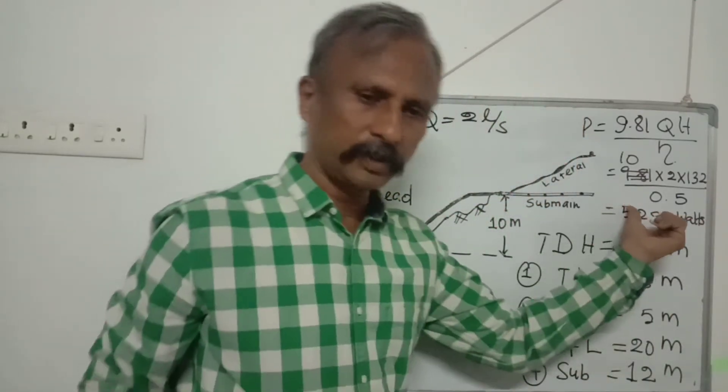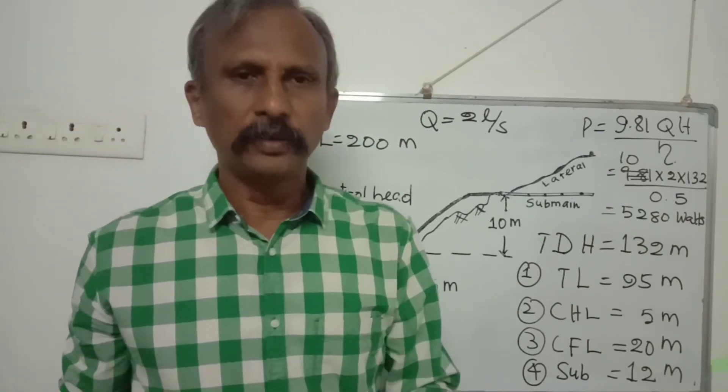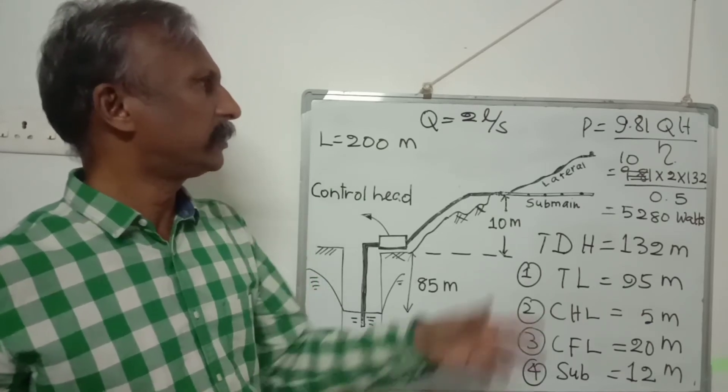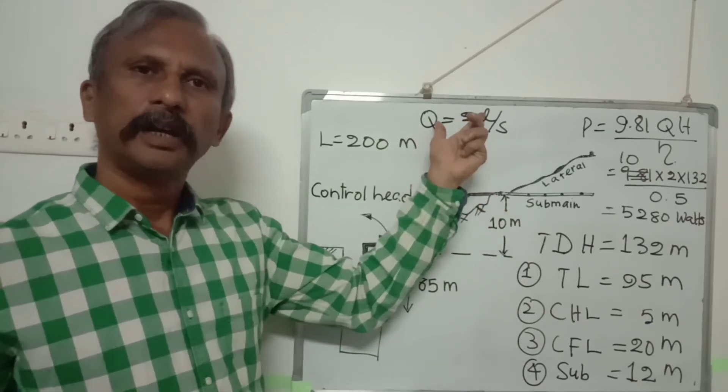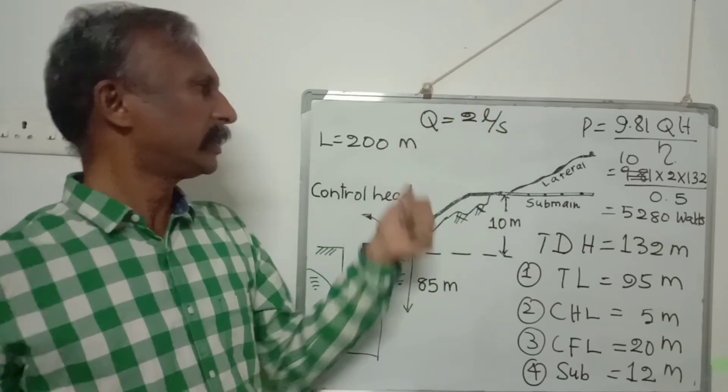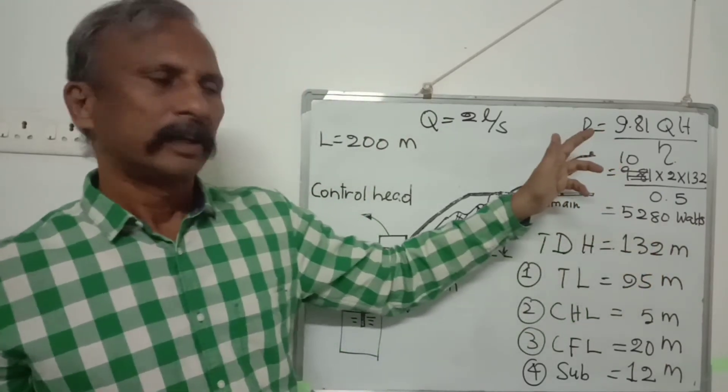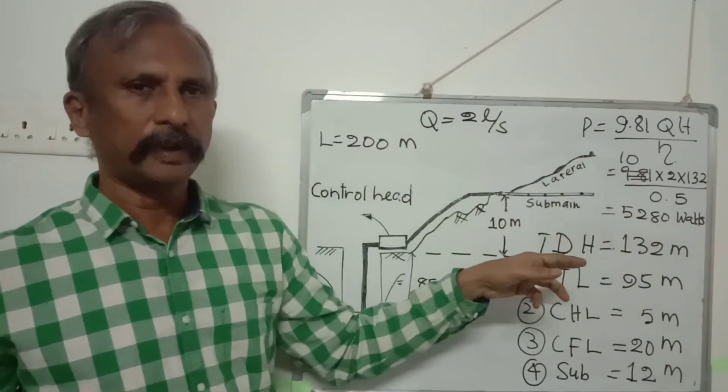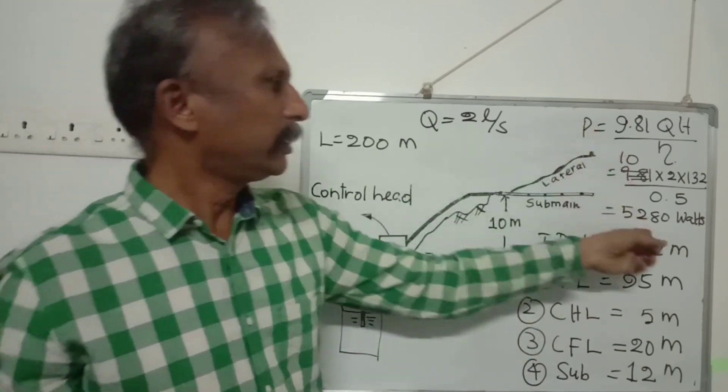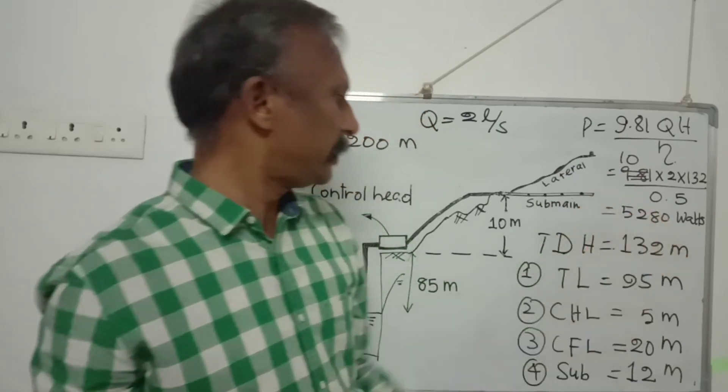So it is approximate only. When you go to market and look for purchasing the pump, you should specify that you need a pump which can deliver 2 liters per second at the pressure head of 132 meters. When you purchase that kind of pump, it will automatically have the power of the pump very near to 5.2 kilowatts.